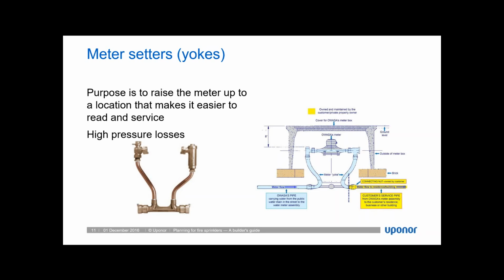If it's known ahead of time, and if it's possible to select larger sizes, it may not be a complete deal breaker for a sprinkler system to have a meter setter installed in the supply line. The issues come in when, like I said, it's not initially designed into the system, or if it's a smaller size. For a 3/4 inch meter, the components of the meter yoke are often as little as 5/8 for the tube that goes up to the connections on either side of the meter. Additionally, the components that can be incorporated into that meter yoke can be varied. There can be check valves or pressure-reducing valves incorporated at those junction points where the meter is sitting.